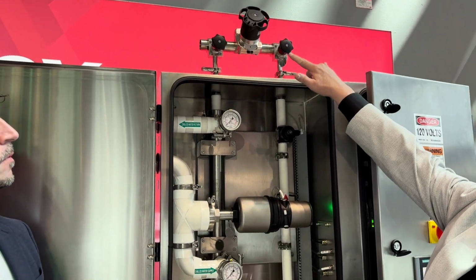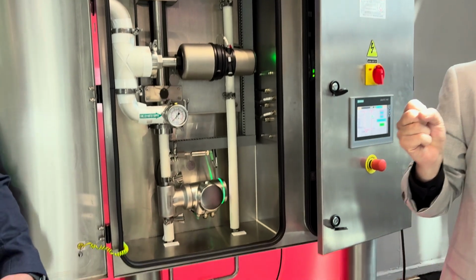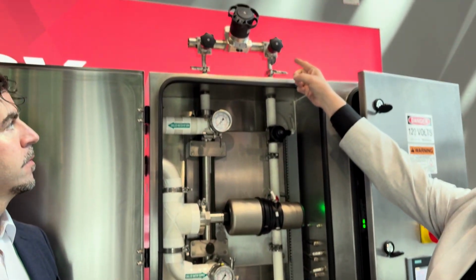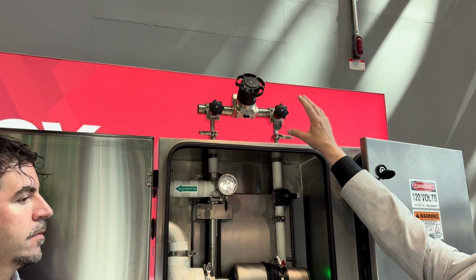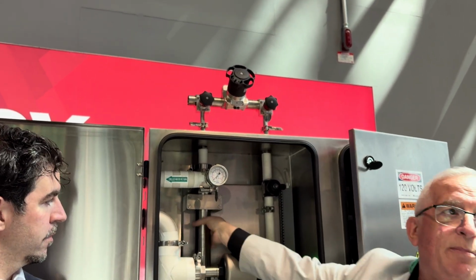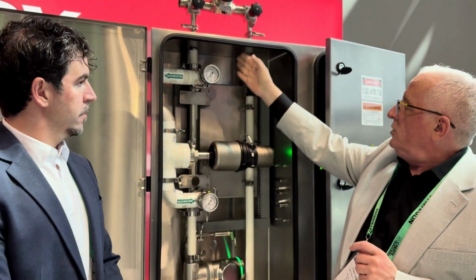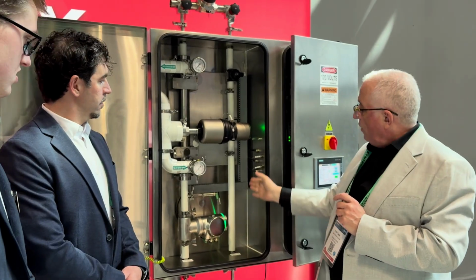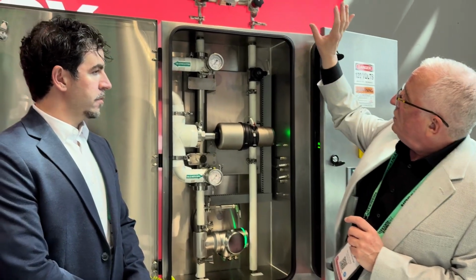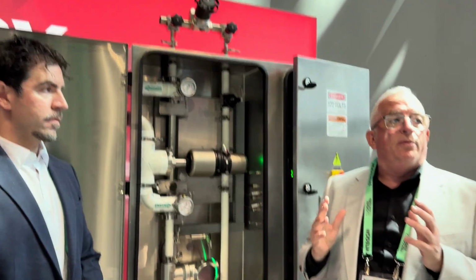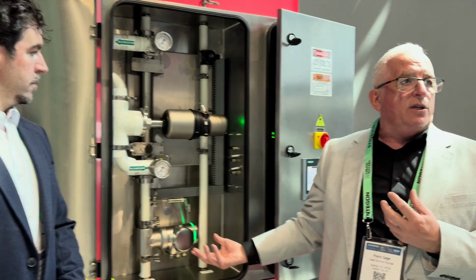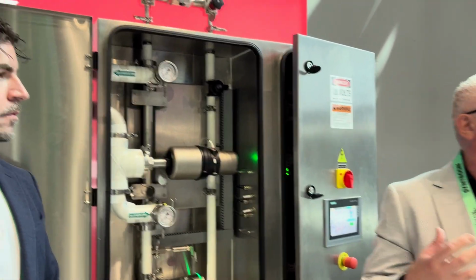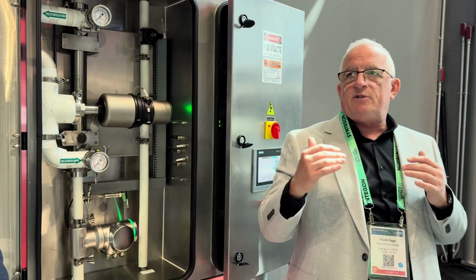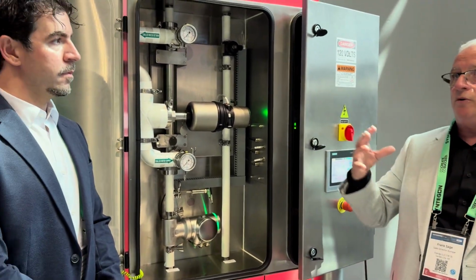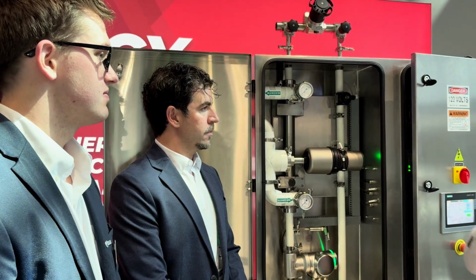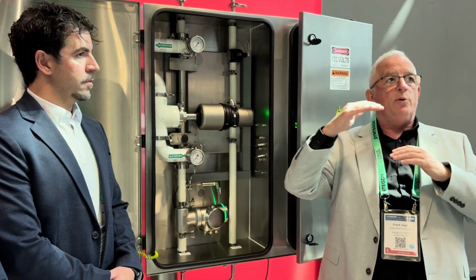So in process, you have your main WFI header. You've got two isolation valves here, zero static, just merely for maintenance and isolation. This valve here, when you're commissioning, we set this valve, we use a strap-on flow meter here in the subloop until we can measure 1.2 liters per second flow through the loop. When we have that measured, we set that, and that's it. It's set up. So again, this is quite a basic unit. We do very complex units for chromatography skids where multiple process steps are needed. So as you would know, with the chromatography valves in this as well. So multiple process steps, variable flow, variable temperature, maybe up to 6 process steps.